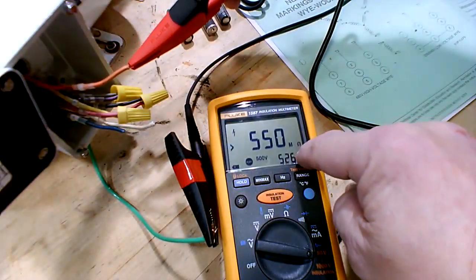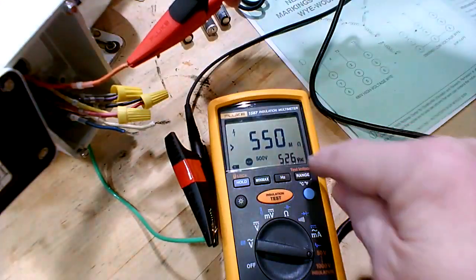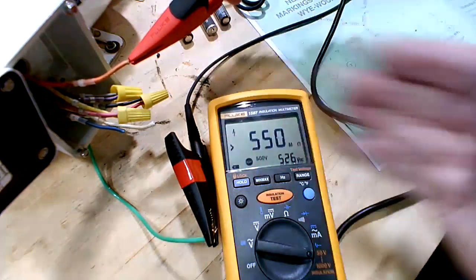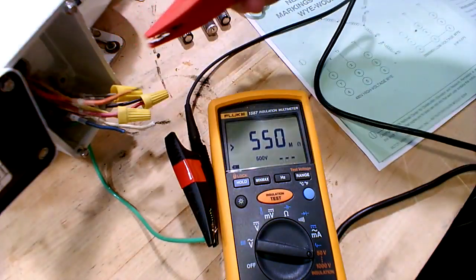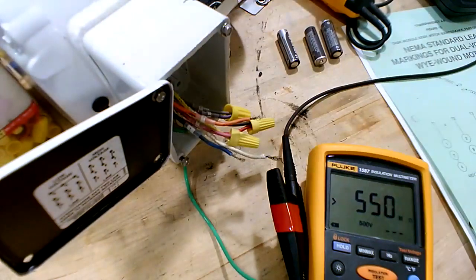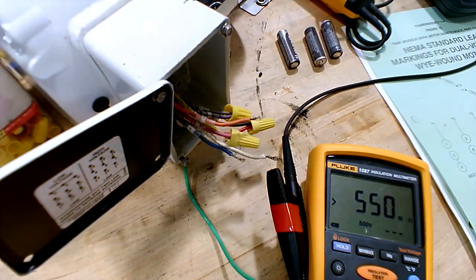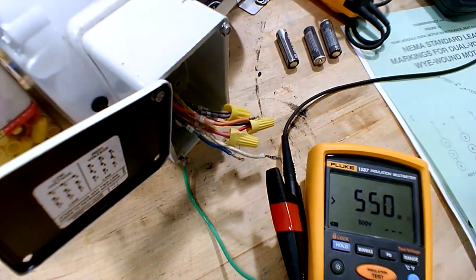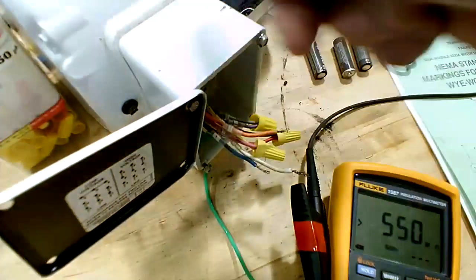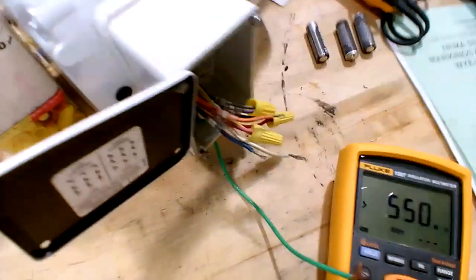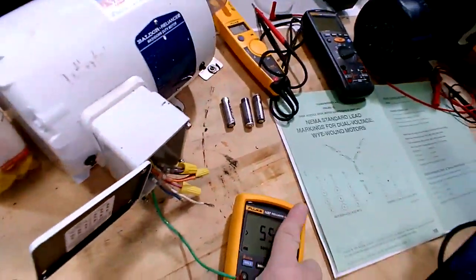That's the voltage it's producing that it's sending out to the motor. It's sending out 526 volts DC, shooting out to it. Okay? So each leg to ground is fine. And then the one over here is actually bad. So we're going to do a continuity test through this one. But before we do it, while we're doing leg to ground, we're going to shift over to this other motor that we know is bad.